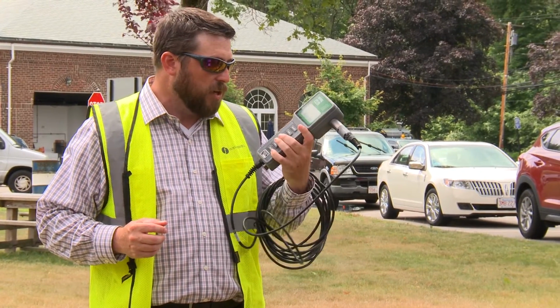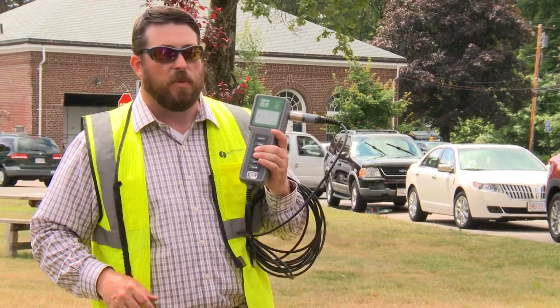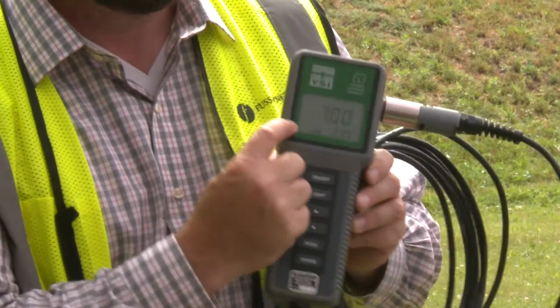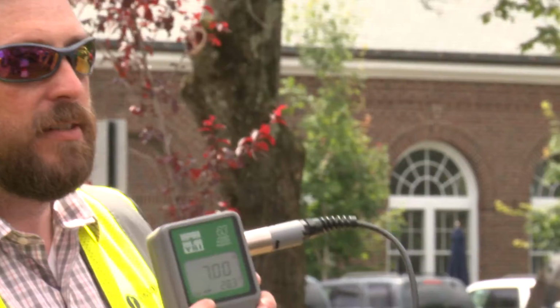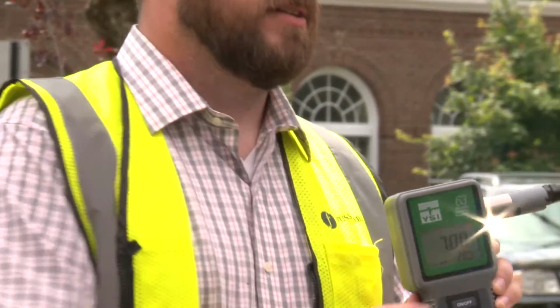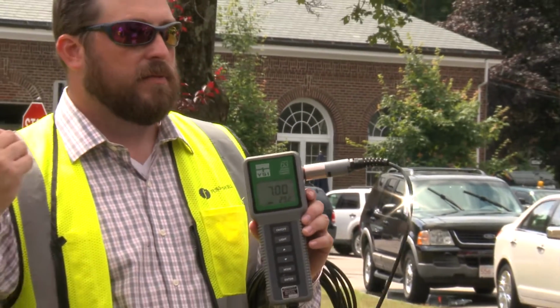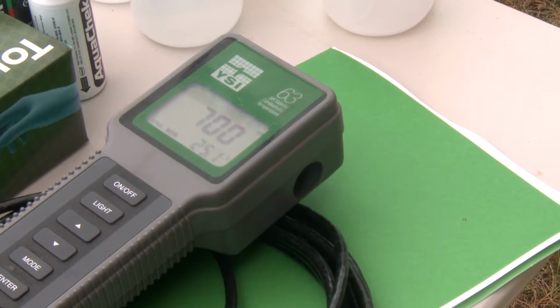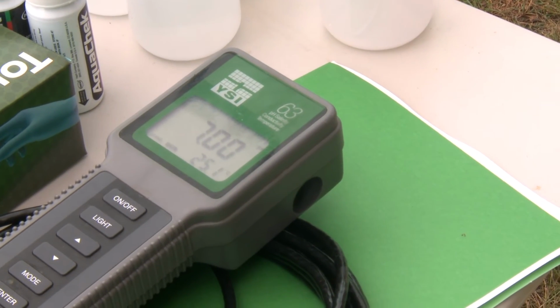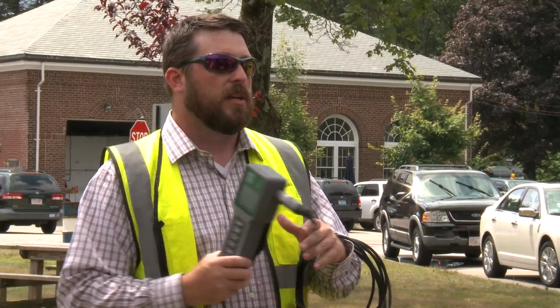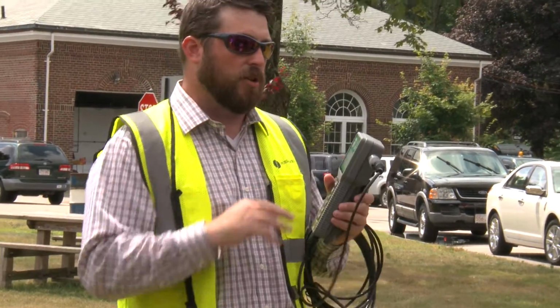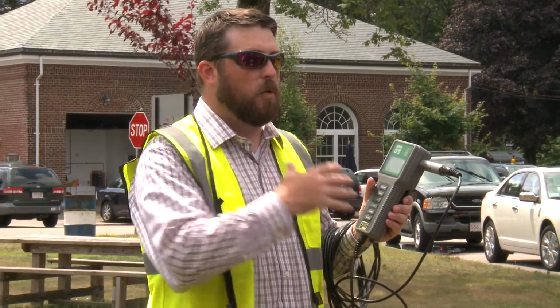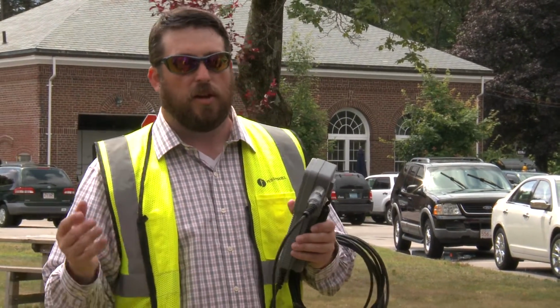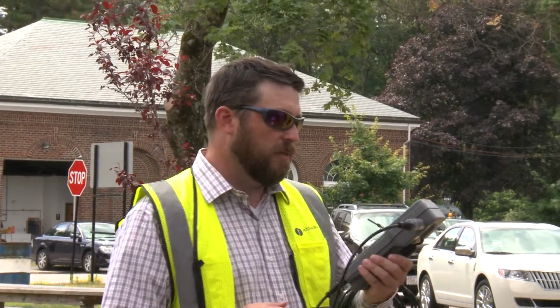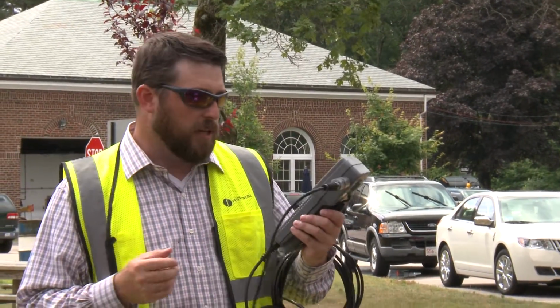For this unit, calibration is fairly simple. You just press these two buttons at the same time. On this unit, it's asking for a standard of 7. It's telling you it's in calibration mode. Put it in standard 7. When it stabilizes, this particular unit has an indicator: the decimal point stops blinking. Hit enter, move to your next standard. It'll automatically sense which direction you're going. Your standards for pH typically run 4, 7, and 10. This particular unit can also use 4.01, 6.86, and 9.18 if you want to get super technical.